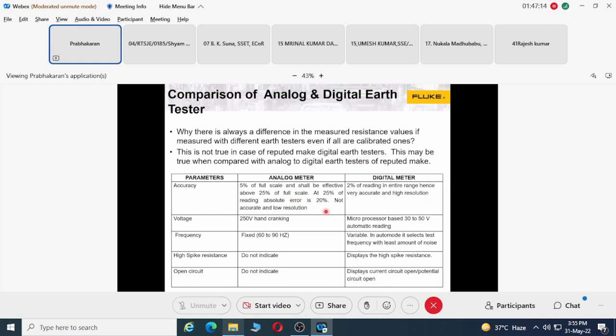Then voltage levels: 250 volt hand cranking. When you generate voltage using hand cranking, it will be difficult to achieve and it takes time. Here the voltage is automatically generated internally using microprocessor control. That means you will have a very steady voltage, and you may get even 5% accuracy, with a precise 30 volt or 50 volt output.